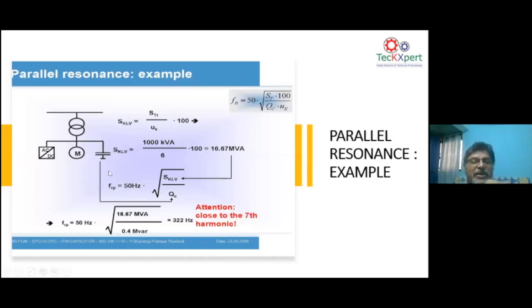Now you should look at this. If you have a transformer of 1000 kVA, and you are connecting a capacitor, let's say a 400 kVA capacitor, to the transformer, and you have an inductive load and also some AC DC rectifiers, that means you have a nonlinear load in a network connected with capacitors. Then with a capacitor of 400 kVA, there is a mathematical relationship that gives the natural frequency of this network.